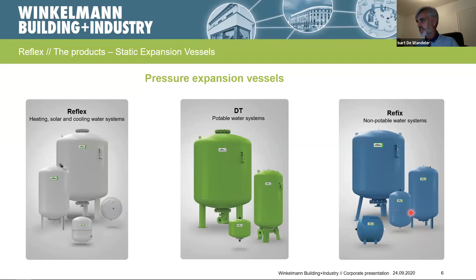we can provide systems with membrane, where above you always have your filled air, your nitrogen or air that is in the vessel, and below you always have your water and of course your water contents of your system. Here you can also see the water is always in contact with the metal of the expansion tank. If we work with the bladder, your medium is a little bit better protected. Why? Because the water will always be inside a bladder. So that means that there is also no contact of the water with the metal of the vessel. So those two are the big main differences between a diaphragm and a bladder vessel in the Reflex range.